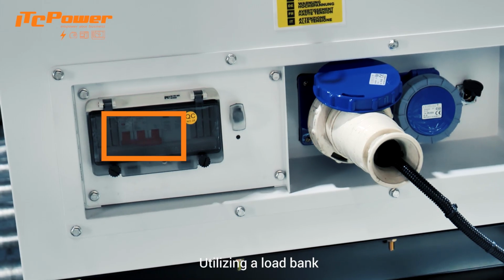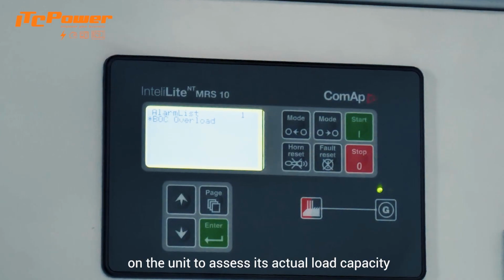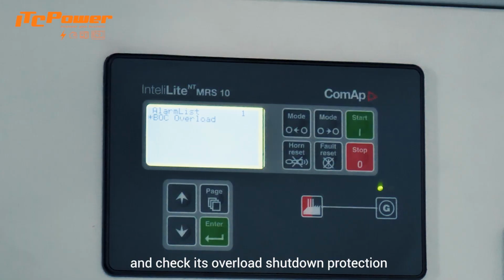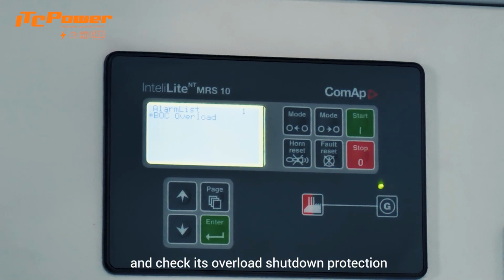Utilizing a load bank, we will perform an overload test on the unit to assess its actual load capacity and check its overload shutdown protection.